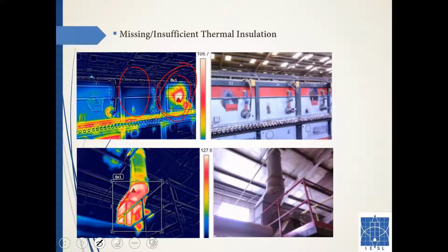But when something like this pops up, that's bad insulation. You can also see it visually, the visual image certainly confirms it. Right here, there used to be a point like this, but obviously they repaired it. So that's missing insulation, and on the bottom we have a stack where the kiln exhaust is conveyed. You can see here in this area, the insulation is missing, and from here that's radiant heat.